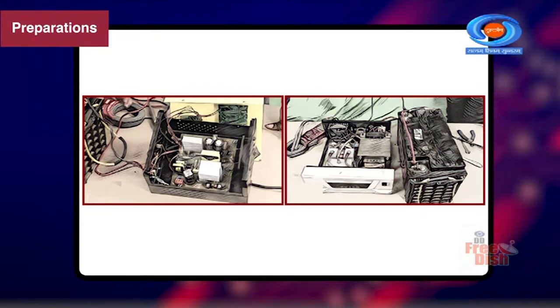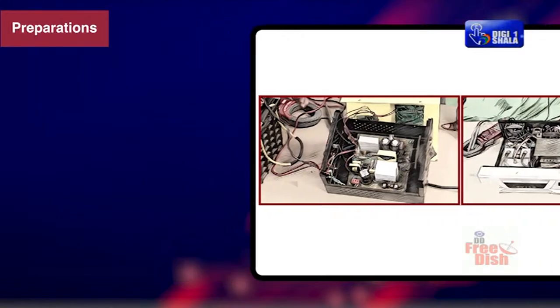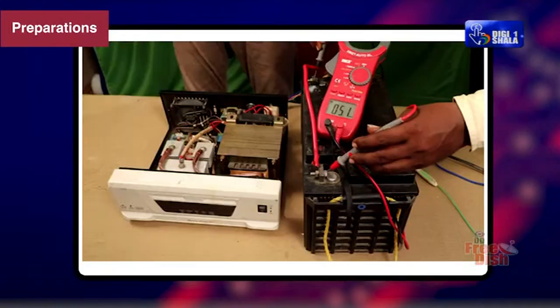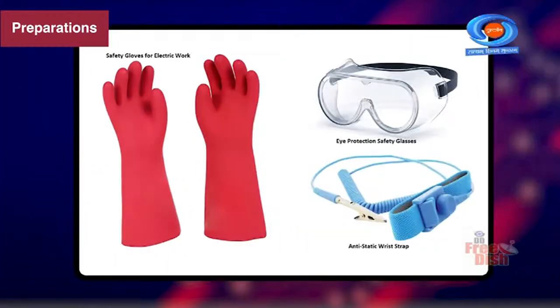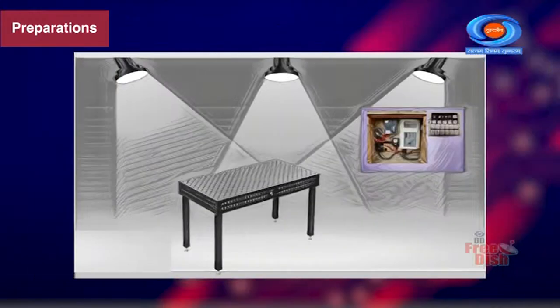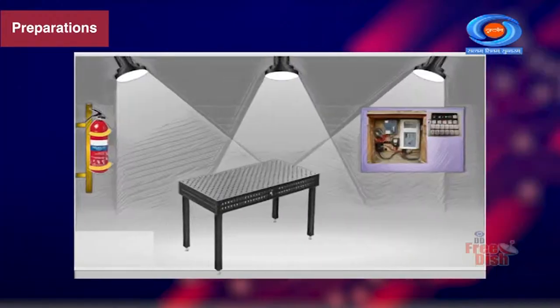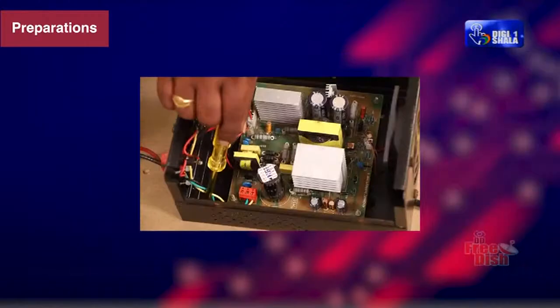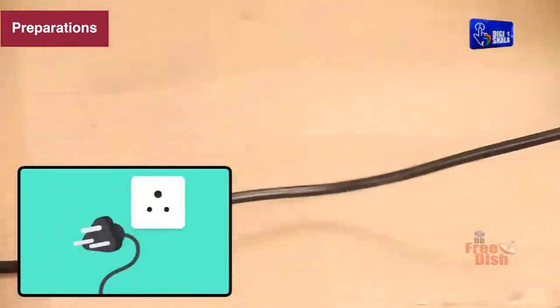Let us take a look at the preparations for maintenance, servicing and troubleshooting of a battery charger and inverter. In this exercise, our first task is to service and troubleshoot a battery charger. Ensure your personal safety by wearing appropriate protective gear such as gloves, safety glasses and an anti-static wrist strap if necessary. Find a well-ventilated area with proper lighting for troubleshooting. Ensure you have a clear workspace and access to a power source for testing the charger. Keep a fire extinguisher nearby as a precaution. Make sure the charger is unplugged before starting any work.